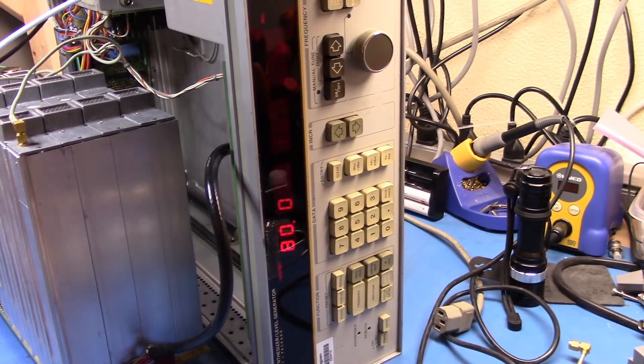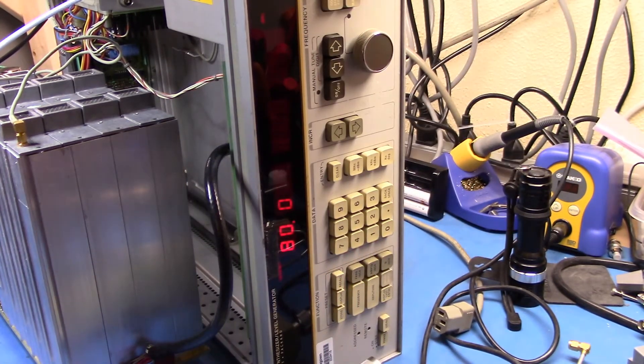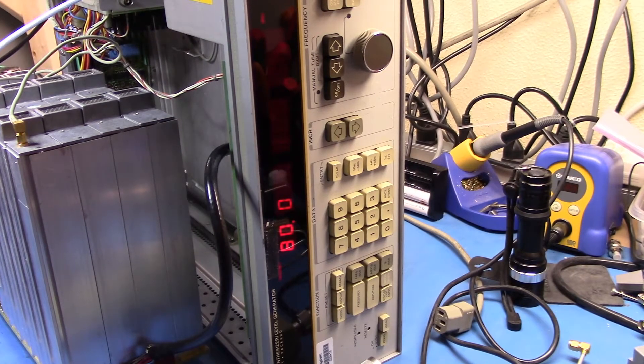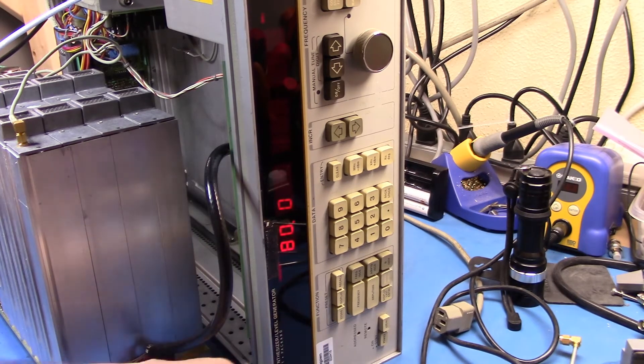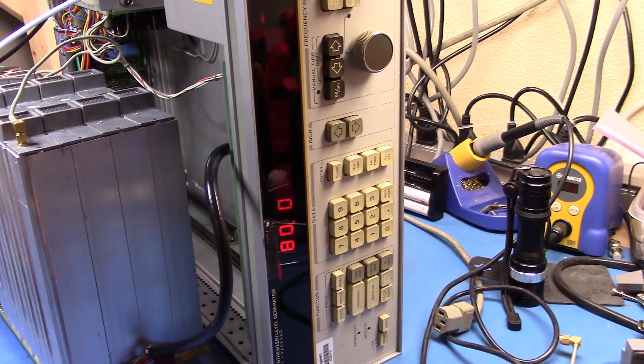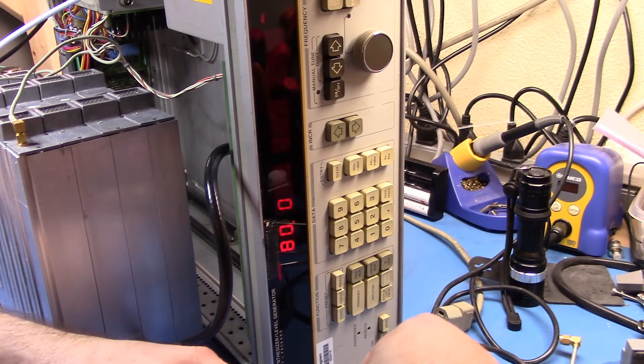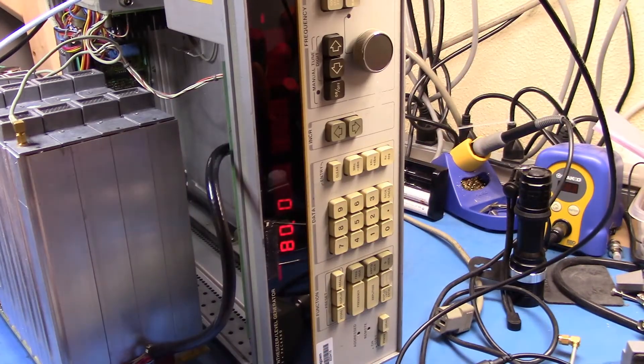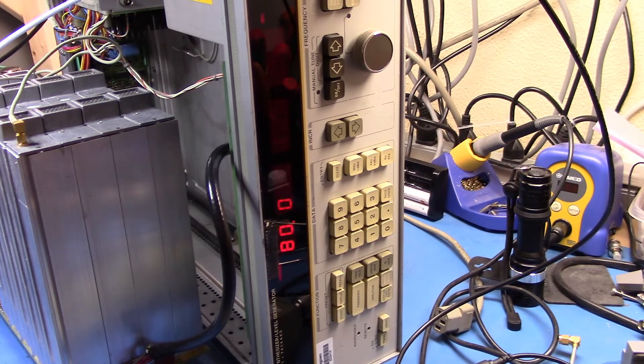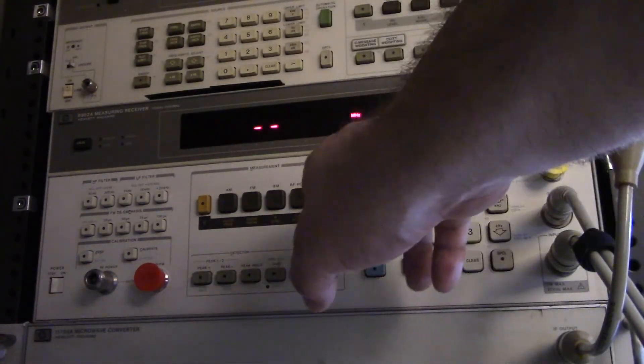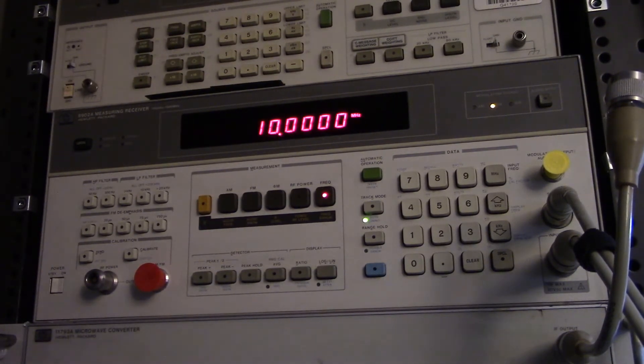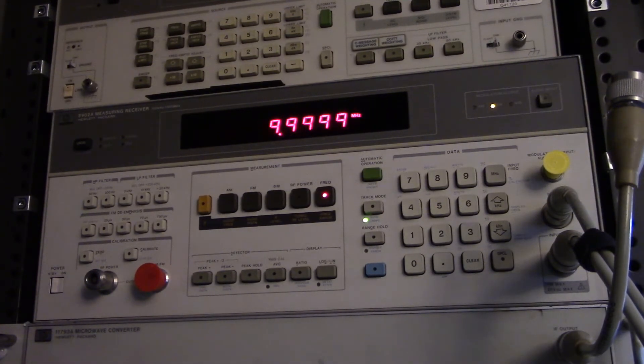Now I have my 11722A. Let's grab a couple of little adapters. What I'm going to go do is just put this BNC adapter into my power sensor, and then we're going to connect this guy to here. Now that we've got that, I can go and do the piece of work on the 8902A. We're all hooked up. Now I have a 10 meg signal coming out.